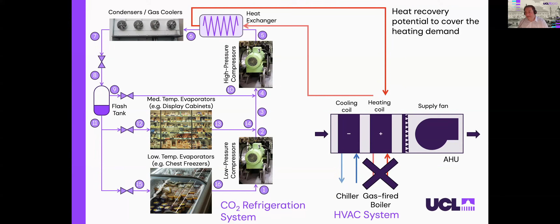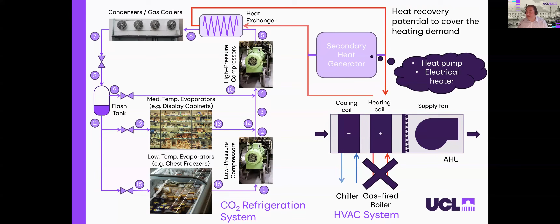What we wanted to explore is - remember, refrigeration is the largest consumer, heat taken from those products and cabinets is rejected to the outdoor air. We wanted to explore the opportunity for capturing that rejected heat and try to offset some or all heating requirements provided by the gas-fired boiler, and to see how much energy we can recover, and if there is any need for a secondary heat generator, and what would be the outcome if we apply a secondary heat generator using some electricity-based technology such as additional heat pumps or electrical heaters.